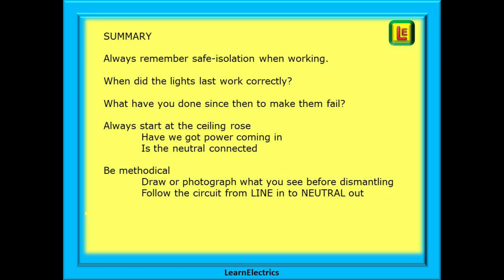And there we have a few faults for you to consider and understand. Always remember safe isolation when working. Ask the customer: when did the lights last work correctly, and what have you done since then to make them fail? Always start at the ceiling rose — have we got power coming into the room? Is the neutral connected? Does it return to the consumer unit? Without a complete circuit, nothing is going to happen. Be methodical in your inspection and testing. Draw or photograph what you see before dismantling — at least then you can get back to where you started. Follow the circuit from where the line comes in, through the switches and lamp, back to the ceiling rose, and then through the neutral and out of the circuit.